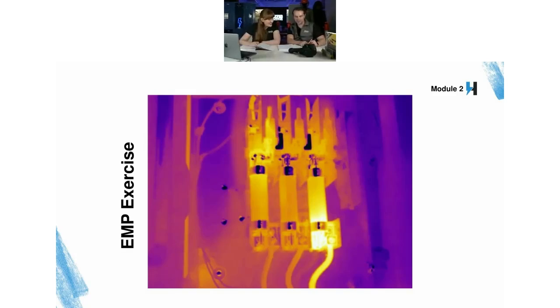It says, all equipment shall perform infrared thermography. Condition 1, 12 months. Condition 2, 12 months. Condition 3, every 6 months. Right. So an infrared scan minimum every year. We've been getting them every year. So Lisa, that would make you compliant with the 70B as long as you don't have any condition 3 equipment. So we would classify this condition 3. We would come in and scan it and find that you would make corrective actions, but you would still need to check it again in 6 months. If determined that there's no more heating issues, it could escalate to a condition 1 or a 2.